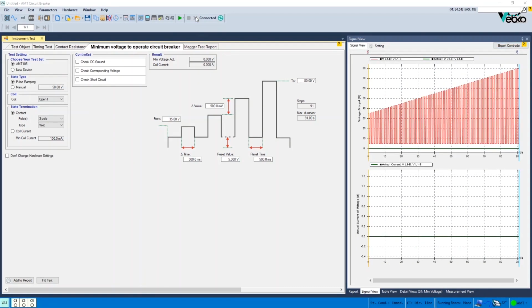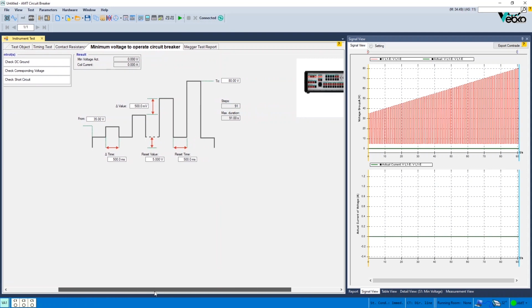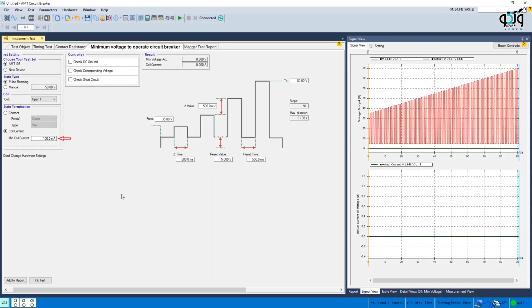In using the coil current method, the wiring is changed and the circuit breaker operation is detected based on the current drawn from the resource. You need to specify the minimum current which is drawn from the device when the circuit breaker operates in the minimum coil current field. Here 100 milliamperes is selected.